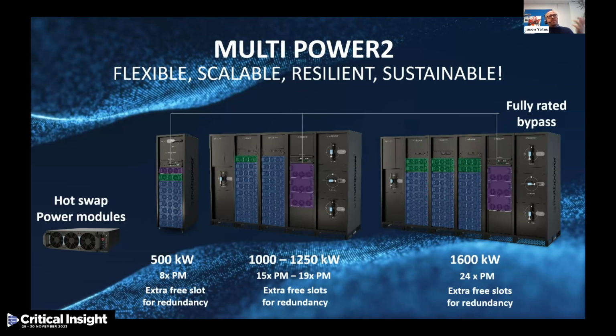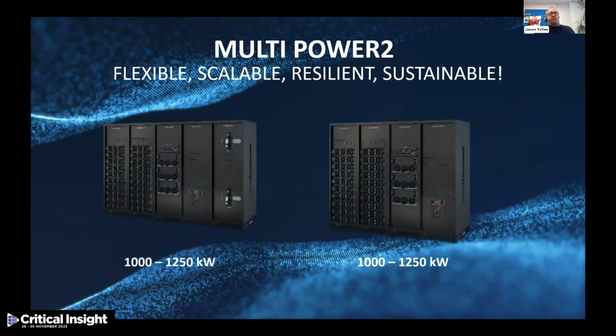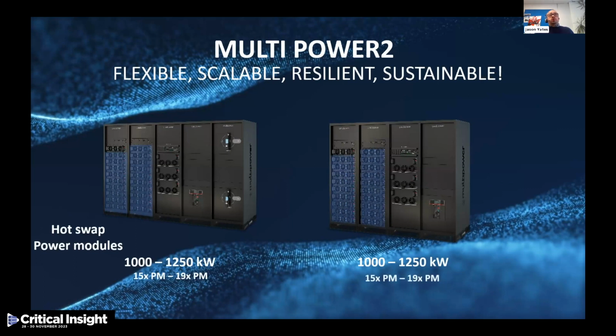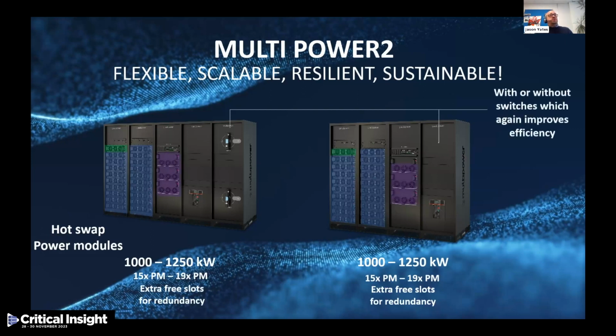And still further, in terms of their flexibility, the beauty of this product is not just about the efficiency levels, it's basically its flexibility to be installed in various environments. If we take a look at the 1 meg and the 1.25 meg, you can see that we've still got the same hot swappable modules. We've still got the same space for redundancy. In this case, you can have it with or without switches, because believe it or not, even the switches alone will create changes in the efficiency because of the losses through the switch.